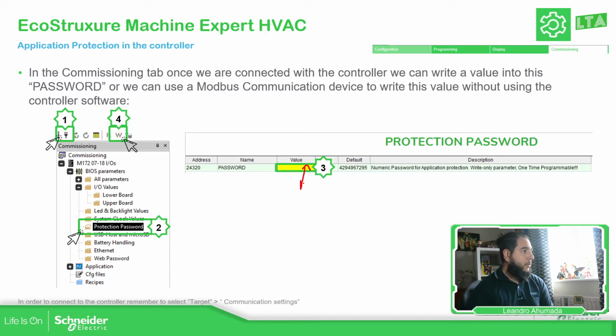So you're going to enter the new password here, and then you just write the value. Simple as that. Okay, this is the configuration that you have. One good thing here is that if you're trying to read this, for example, using IO scanner for all the controllers, or using Modbus in order to read this register, you are always going to receive FFF. It doesn't matter if you change something, you just receive the information like all the bits are true, which is good because this part is protected.